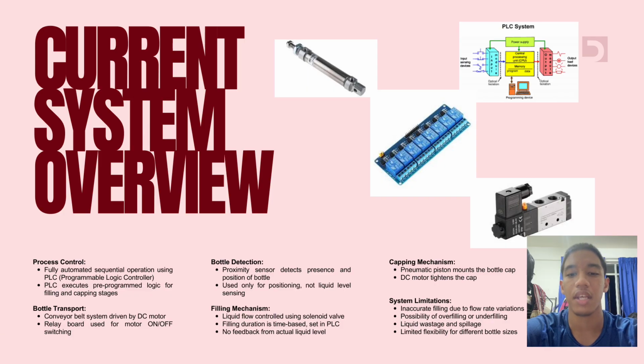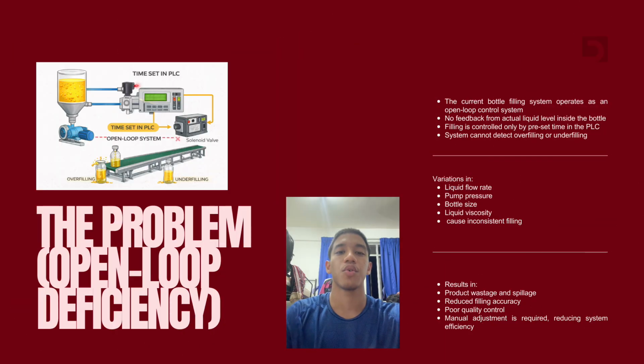It sounds efficient, but in reality, this setup has some major limitations, especially when it comes to accuracy and handling different bottle sizes. So what's the real issue here? The core problem is that the current system operates as an open-loop control system. Essentially, the filling process is blind. The PLC is programmed to fill the bottle based only on a preset time. Because there's no feedback from the actual liquid level inside the bottle, any small change can ruin the batch.